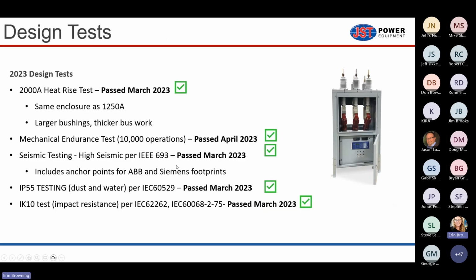For your reference, the design tests that we've completed: 2000 amp heat rise test that was performed back in 2023, and the mechanical endurance test of 10,000 operations. These are all per IEEE. We are seismic rated, high seismic rated per 693. We have means to adapt our breaker to ABB and Siemens footprints for the 15 kV design, 1200 amp.